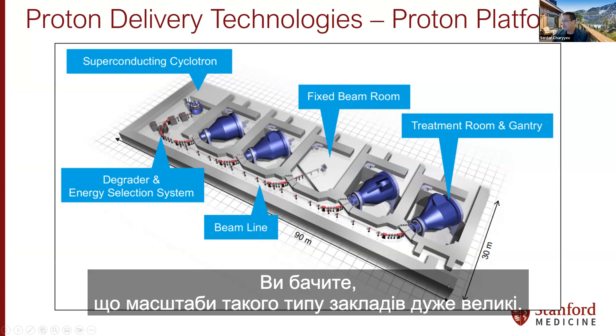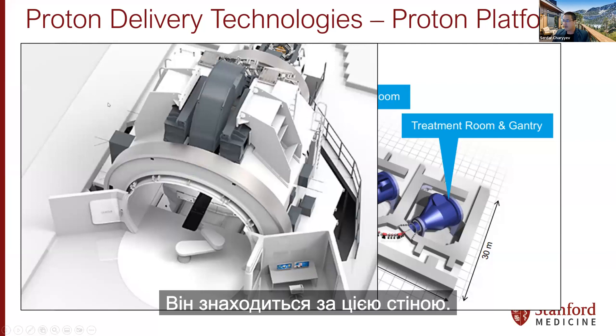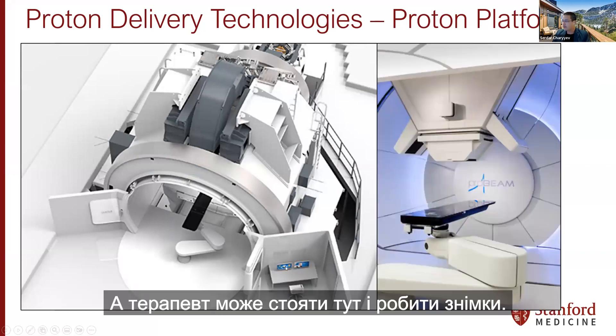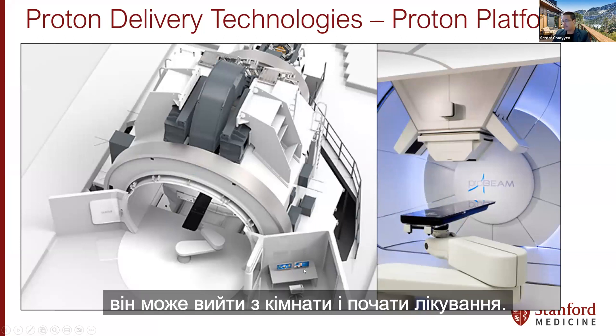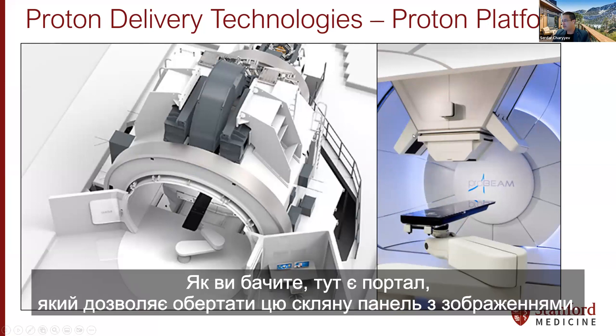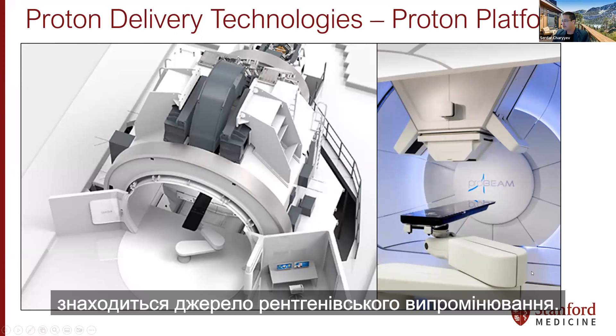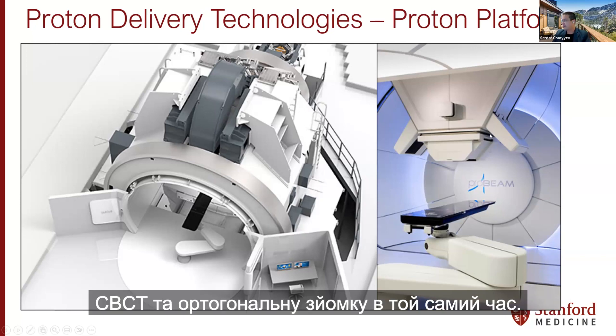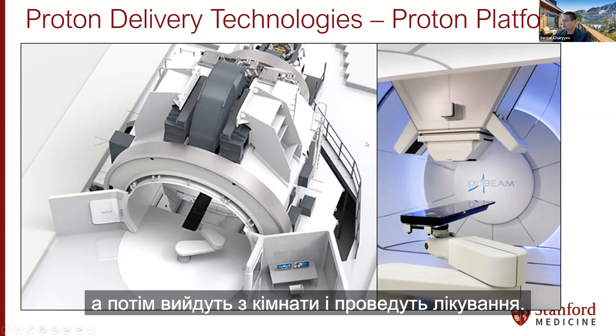Zooming into one of these rooms, the gantry is very large but hidden behind a wall. The patient is positioned on a six-degree-of-freedom robotic arm couch. There is a lead glass window where therapists can stand and image, and after they are happy with the image they exit and do the treatment. The rotating gantry allows the flat panel imager and an orthogonal X-ray source to perform 3D volumetric imaging, CBCT, and orthogonal imaging simultaneously.